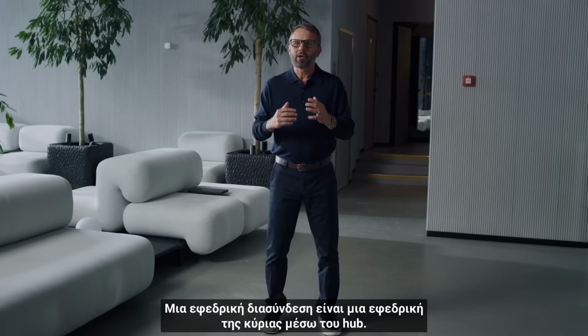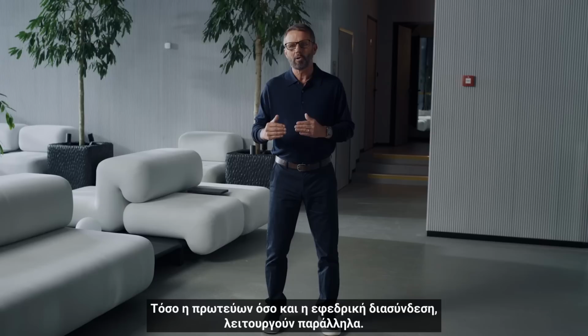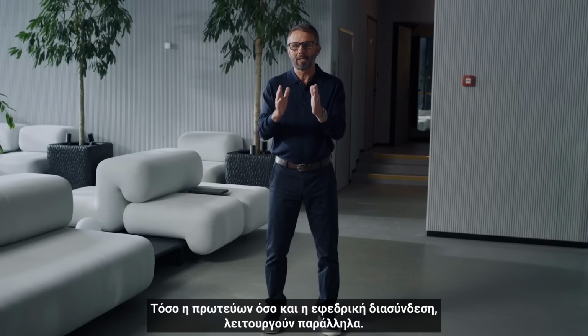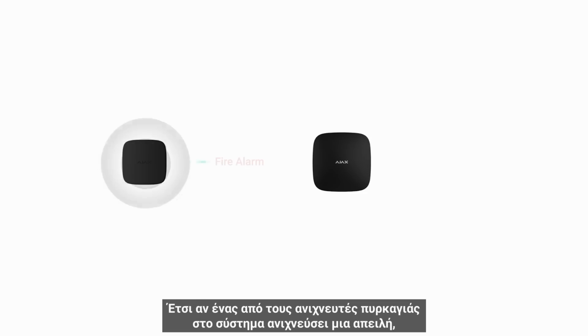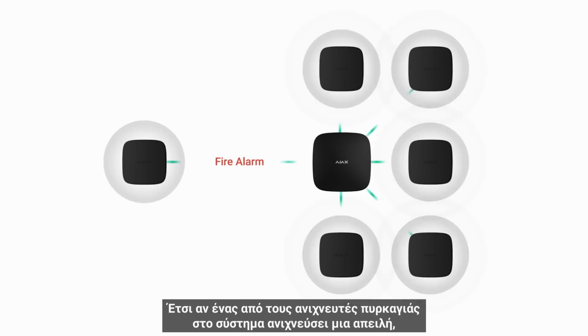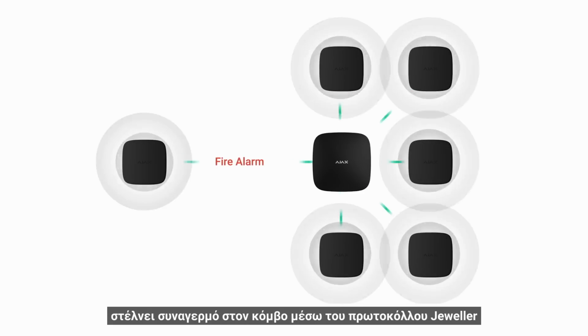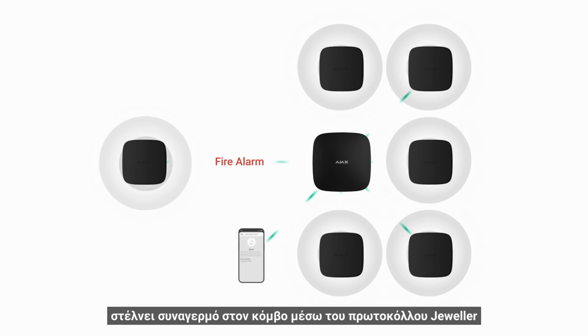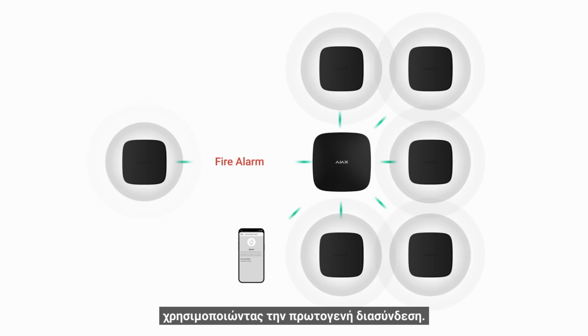How does this work? A fallback interconnect is a backup to the primary one via the hub. Both primary and fallback interconnect work in parallel. So if one of the fire detectors in the system detects a threat, it sends an alarm to the hub via Jeweller radio protocol using primary interconnection.